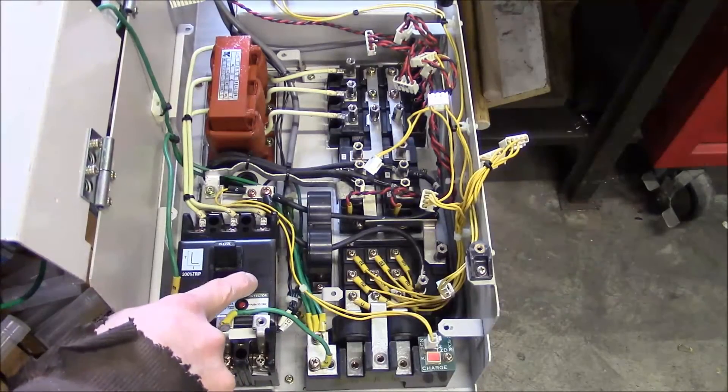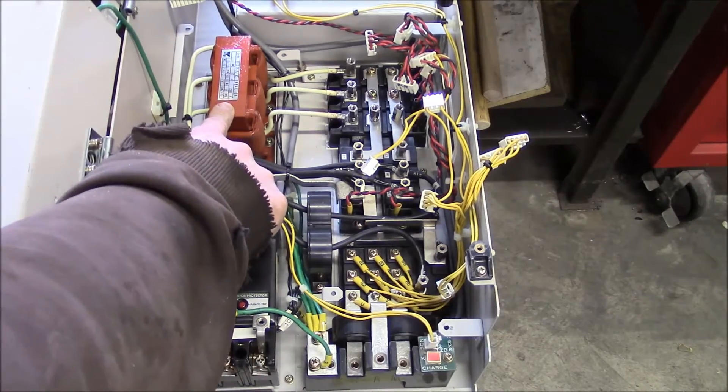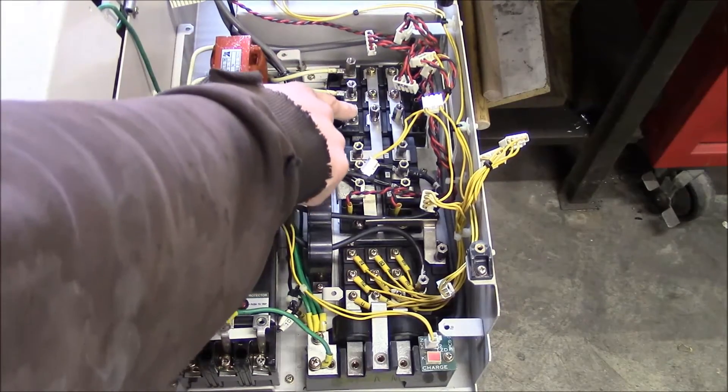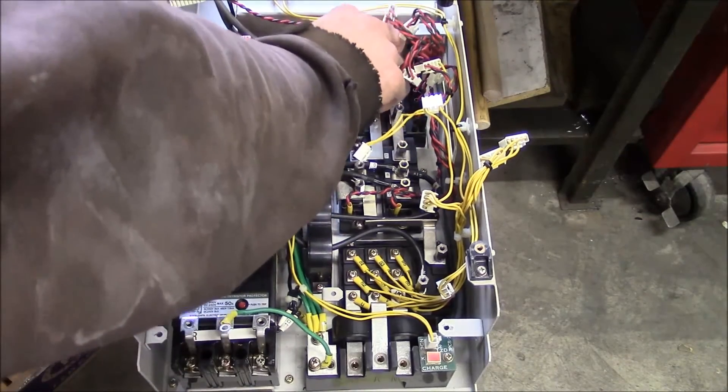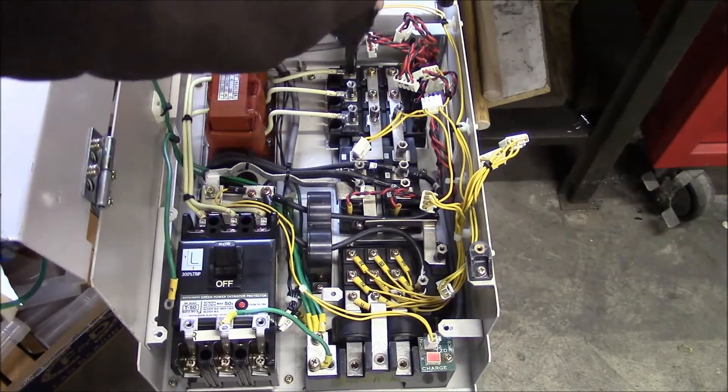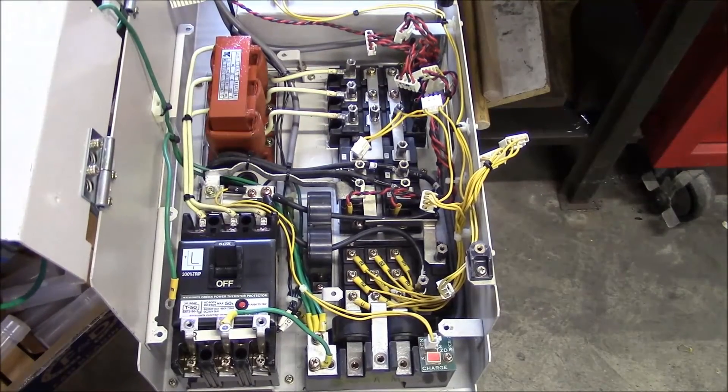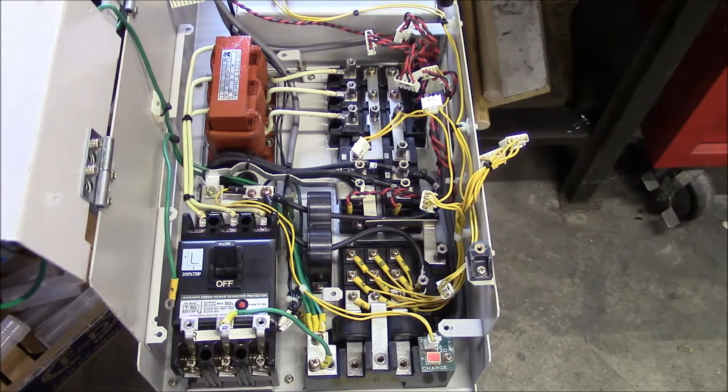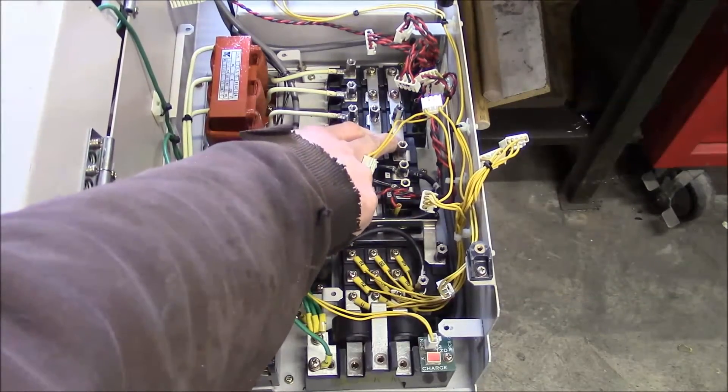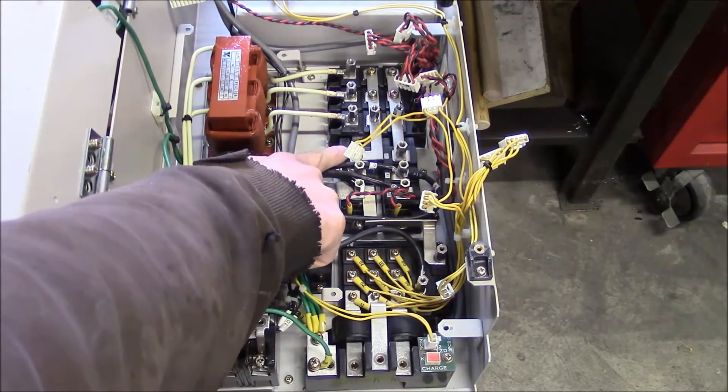So this is the main input on this 50-amp breaker. It goes through a reactor to clean it up and then into these three thyristors. And that's basically a rectifier. Oop, that one's loose. I've got poor quality control here in the repair department. Anyway, so this is the rectification. These two bars here are the DC bus. And then they come into these two Mitsubishi IGBT modules.